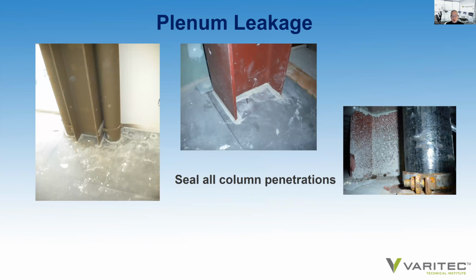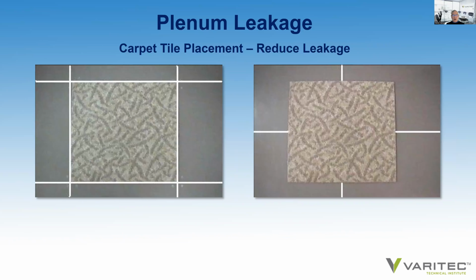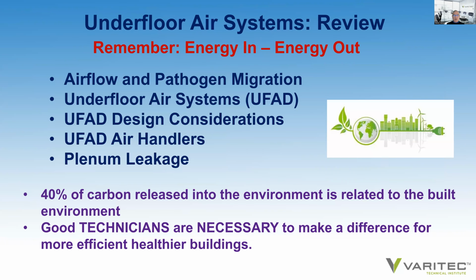All columns need to be sealed where there might be a penetration, so again, to reduce any issue of leakage. And carpet tile needs to be properly installed to minimize the leakage through the floor that, if not addressed, could result in some imbalance of plenum pressures due to leakage points across the floor.